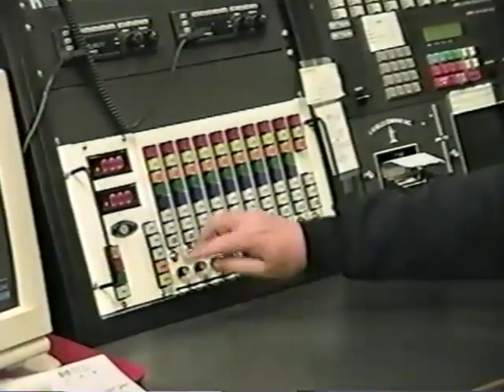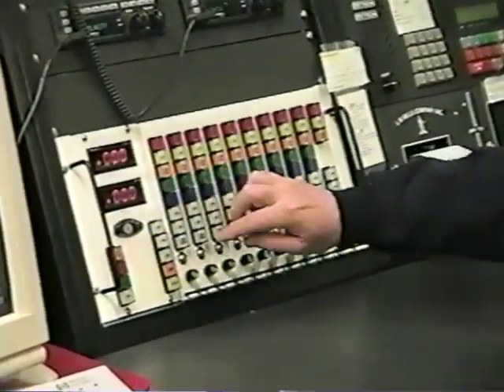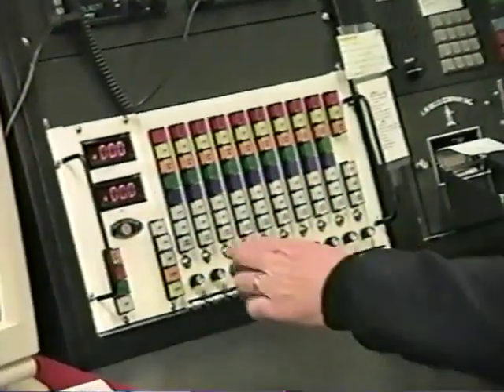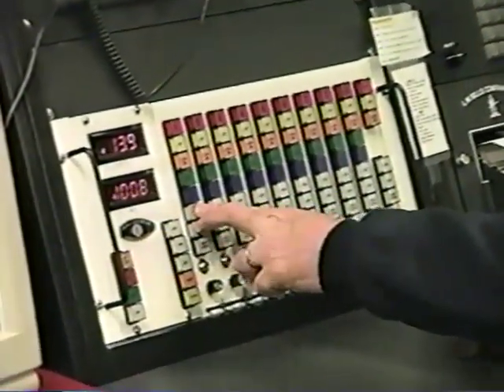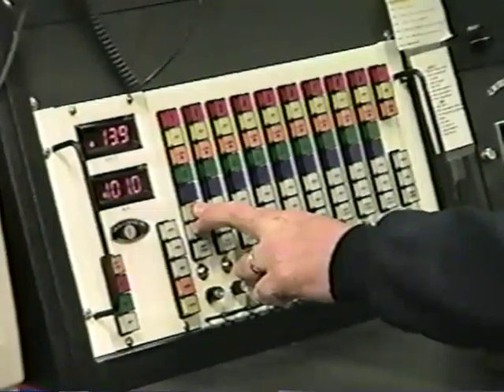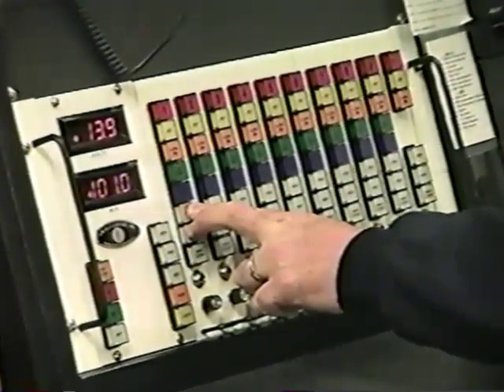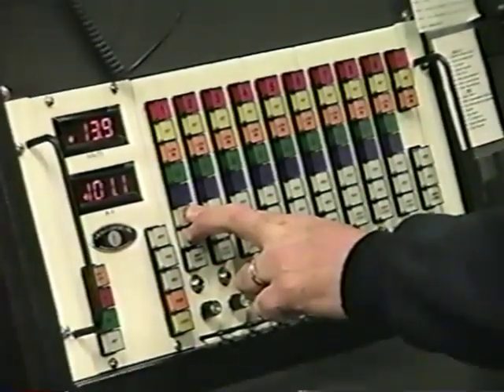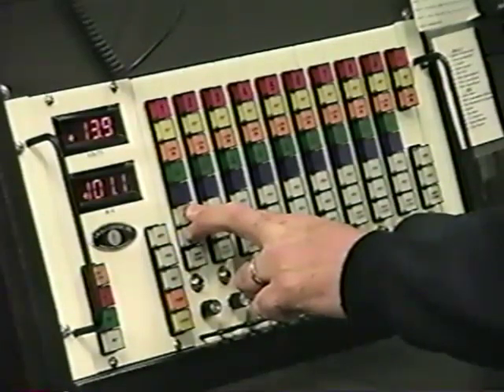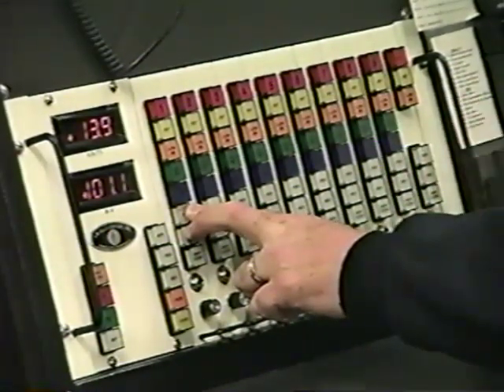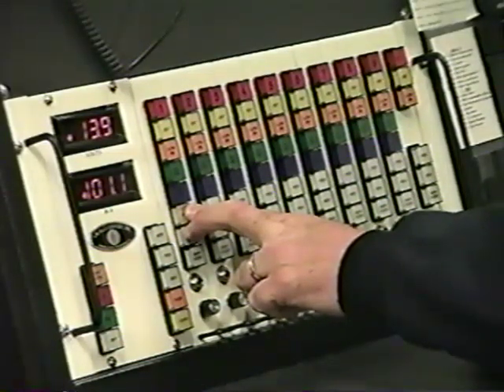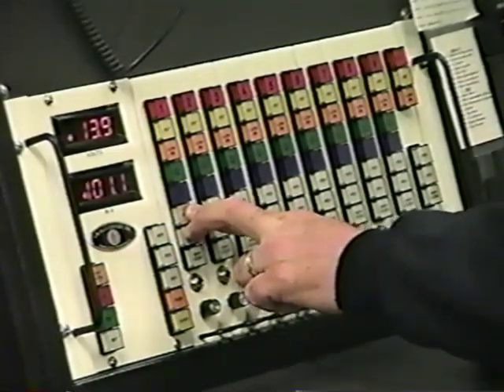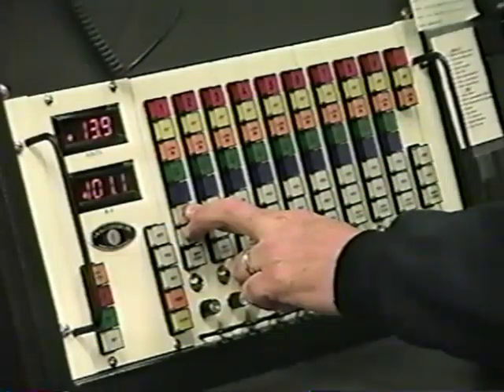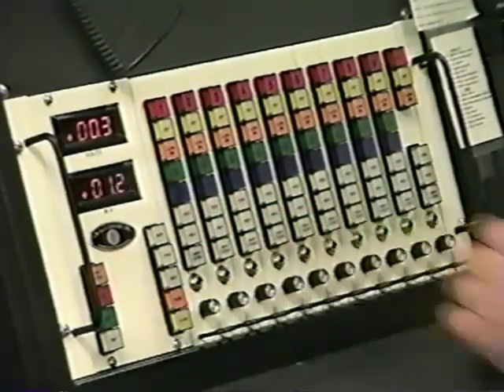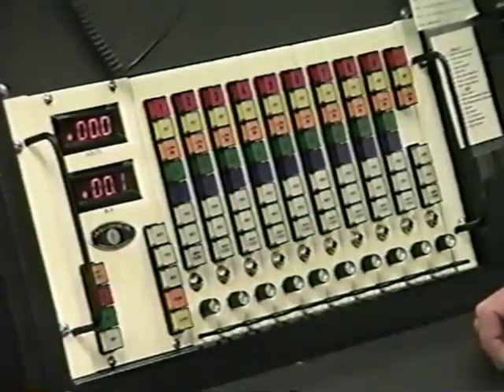The system runs on 100 milliamps, and whatever voltage it takes to get that 100 milliamps out through the number of feet of wire on that circuit. To keep the 100, you can see it's a little high, there's around 100 milliamps, but it takes 13.9 volts to complete that circuit, circuit one, which is Main Street to Eames Street.